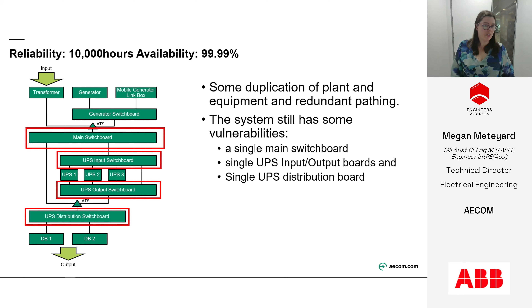There were maintenance activities factored into this network design. For example, there's a generator link box, which allows a temporary generator to be hooked up to let regular generator maintenance be undertaken. The UPS configuration was an N+1 arrangement, meaning that one unit could be taken out of service at a time. And there were dual distribution boards for critical equipment. So that system, as shown, met client criteria.